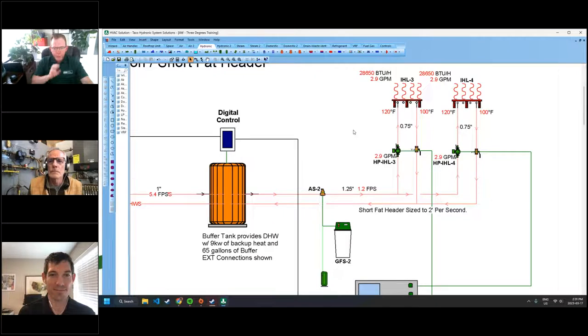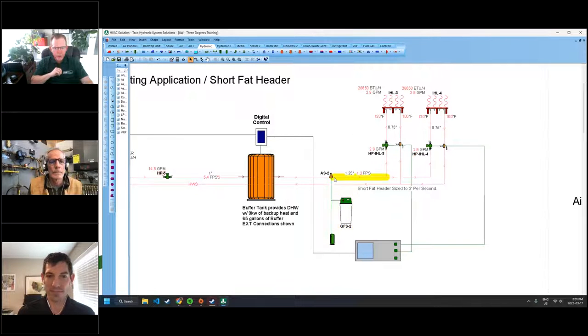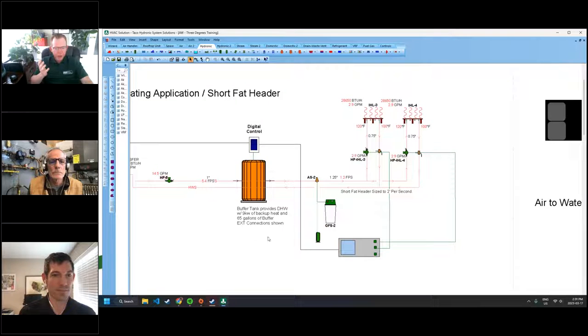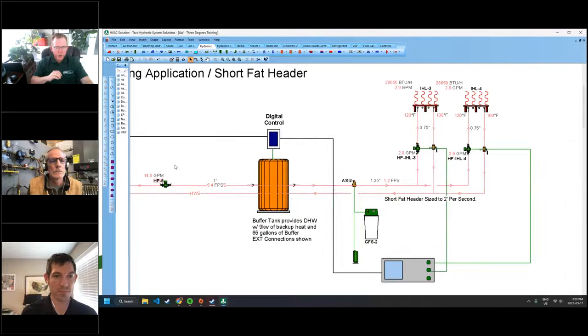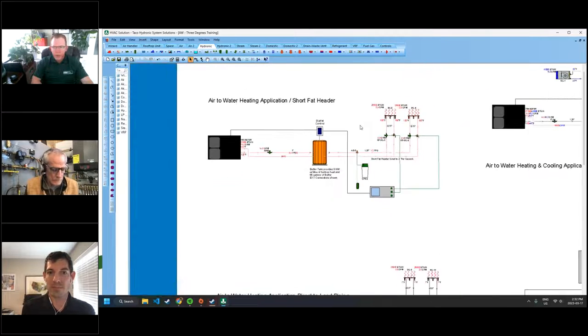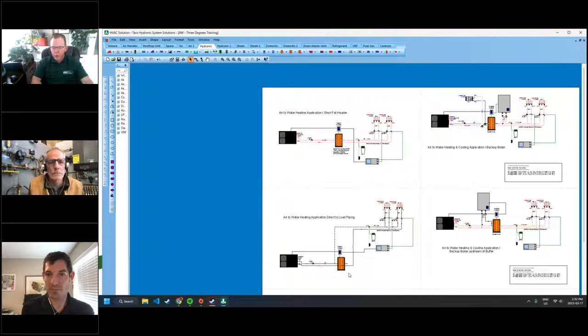So that's a pretty simple setup. We've got a DMF on it. We've got an air separator on it. We obviously have a properly sized expansion tank. The way that we control this typically is I don't care what the outdoor heat pump is doing. I'm not going to have any of the thermostats go back to the heat pump. The thermostats are going to monitor. All they're going to do is pull heat off this buffer tank, and my digital control will monitor that buffer tank and tell the heat pump to come on when the buffer tank needs it. I'm not running my thermostat controls directly back to that outdoor air-to-water unit.